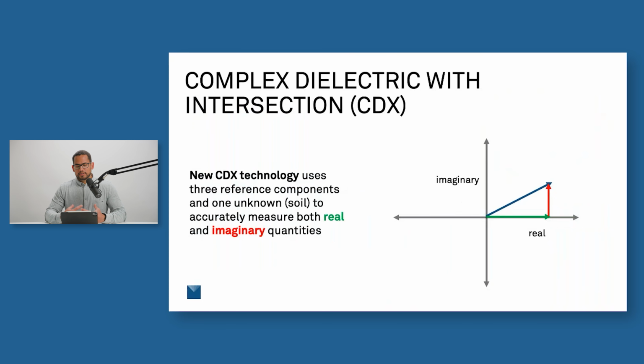Okay, so now we've talked about some of the improvements we've made with the Solix 14 and a little bit of an introduction into the CDX technology. Let's talk about what the CDX technology actually is. We talked about the impact that salts have on the dielectric permittivity measurement. Measuring dielectric permittivity in a conductive sample actually forms a complex number where we have the real portion, or the soil's actual ability to hold a charge, which is what's represented on the x-axis here. And then we have the imaginary portion, or the lossy portion, represented on the y-axis here, which is the imaginary portion of the dielectric permittivity. And so what we're measuring, our apparent dielectric permittivity or the admittance of the measurement, is a complex number of those two measurements.